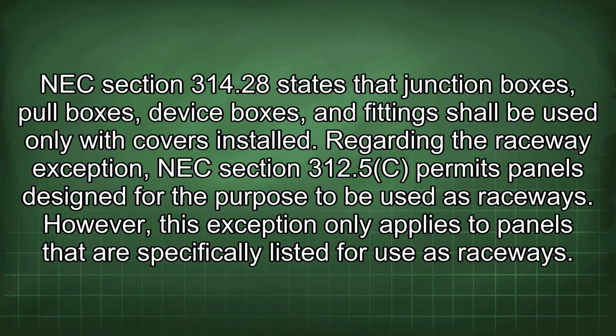Regarding the raceway exception, NEC Section 312.5(C) permits panels designed for the purpose to be used as raceways. However, this exception only applies to panels that are specifically listed for use as raceways.